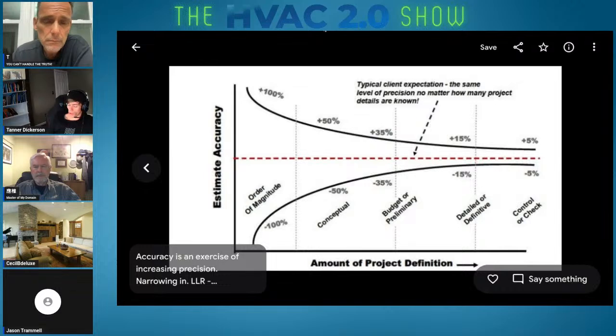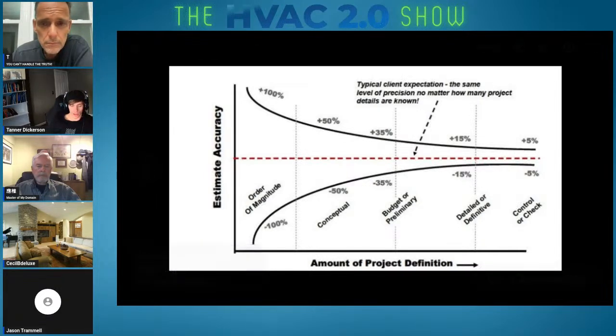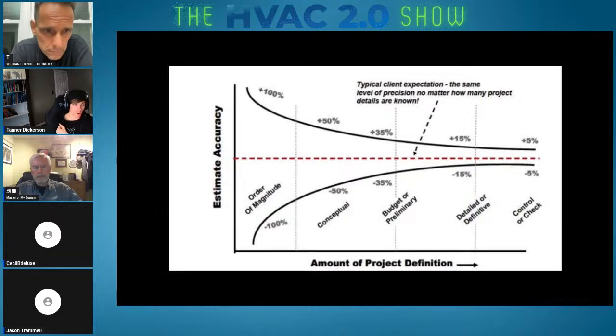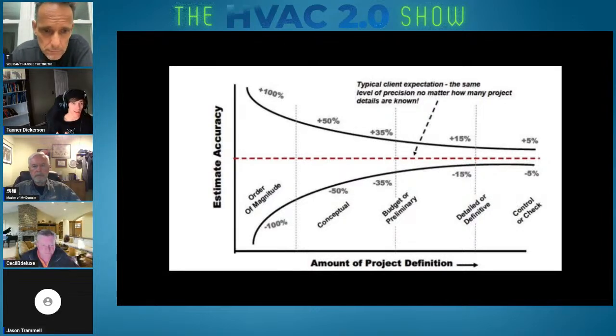In terms of likely load range versus using a load calc, the way I see the likely load range is you're giving a more transparent viewpoint of what a load calc without a blower door is going to tell you anyway. If you're not doing a blower door test, you can do a manual J however you want, but there's a discrepancy of leakage that can cause that number to fluctuate greatly. Unless you know what that number is, the only thing you can do is assume worst case scenario and best case scenario. You're achieving the same thing with the likely load range. The whole reason it's beneficial is that it illustrates exactly what a load calc without a blower door number truly is.